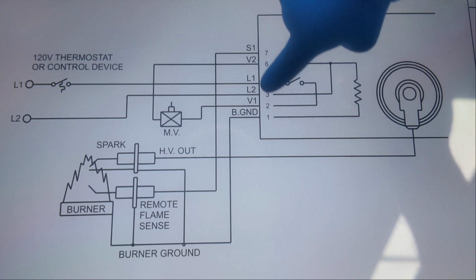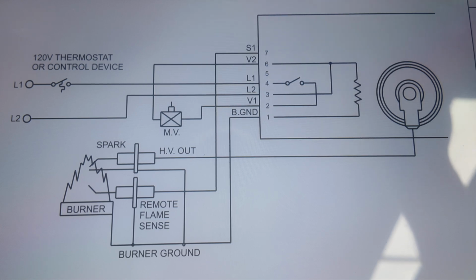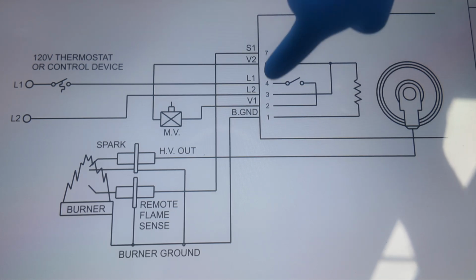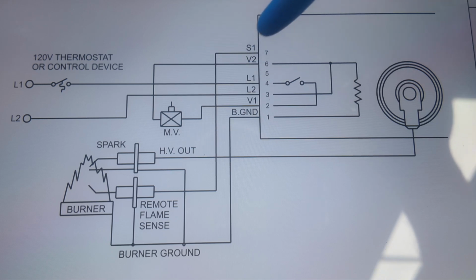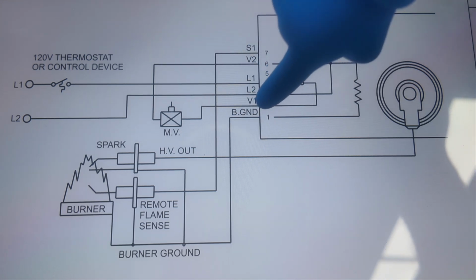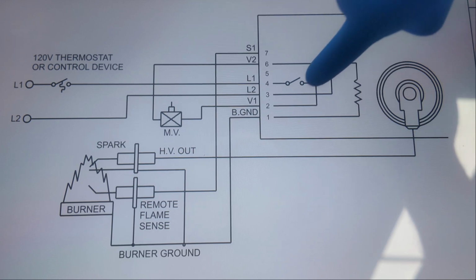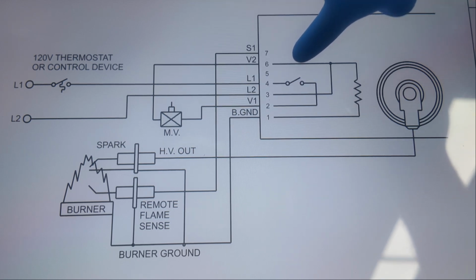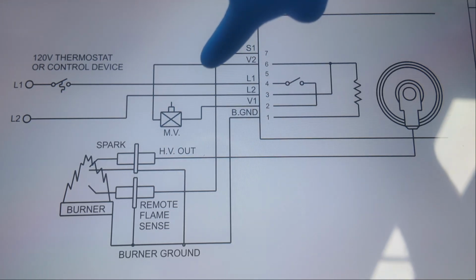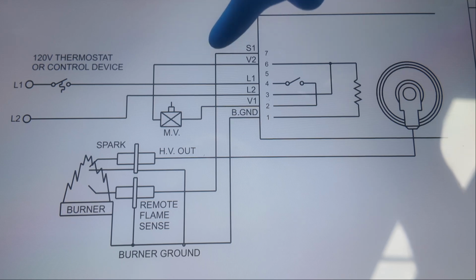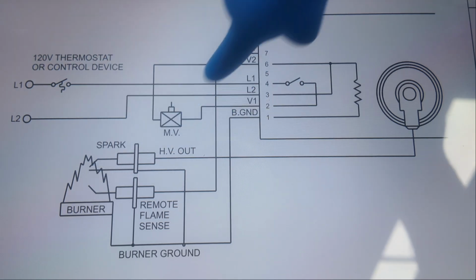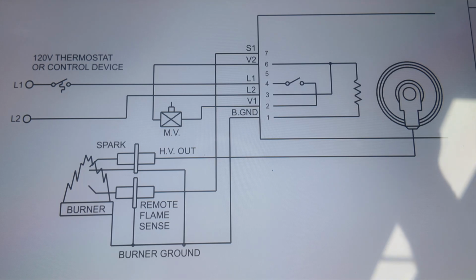But when we get voltage on V1 and V2, it will only be for a limited amount of time. It will only be for maybe 7 seconds or 10 seconds, depending on the board. So it's going to be a limited amount of time. And then if it does not ignite and see flame sensing on S1, it will turn off. Or if you have S1 disconnected, it may ignite, but it's still going to turn off because the board didn't know it ignited. So that's how the Fenwal board works.